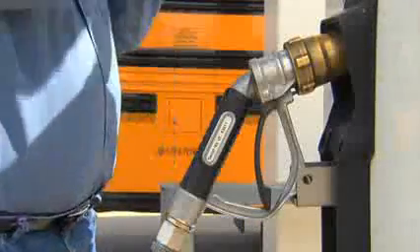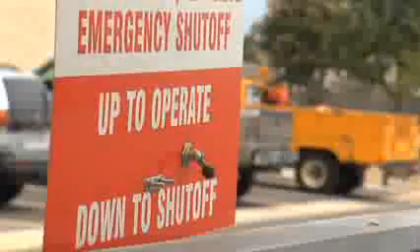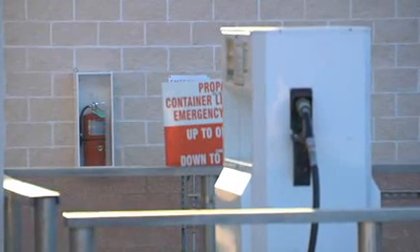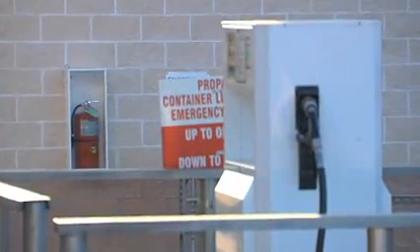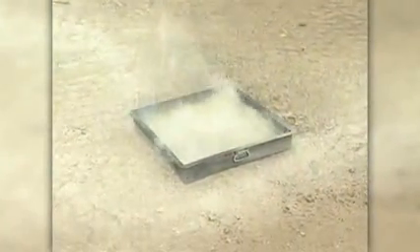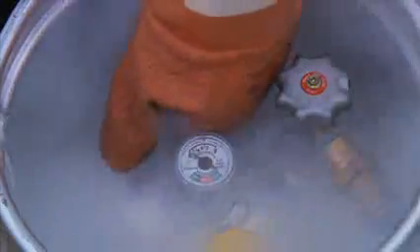As with all combustible fuels, even if you follow all safety precautions, you should be prepared in case an incident occurs. In case of an uncontrolled leak, follow these steps: start by activating your emergency shutdown switch to close the main valve on the supply tank. To prepare for fires, make sure that you have a fire extinguisher mounted close to the filling area. This should be at least an 18-pound dry chemical extinguisher with a BC rating. Keep in mind that fire extinguishers are not intended to put out propane fires and have a limited application area. They are only effective for small fires and can limit the fire to allow enough time for people to escape the area. And if you come in contact with propane on your bare skin, be aware that this can cause freeze burns that may need medical attention.